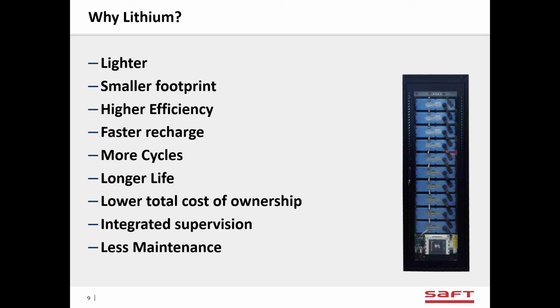The rest of the things, higher efficiency, the batteries don't take hardly any current on float charge, so you aren't always having a float charge current. They don't have to be equalized, so you don't have to put extra energy in to try to equalize the cells. They can be recharged faster, a lot more cycles than lead acid battery. Longer life than lead acid, and that brings you a lower total cost of ownership because you're not changing the batteries.